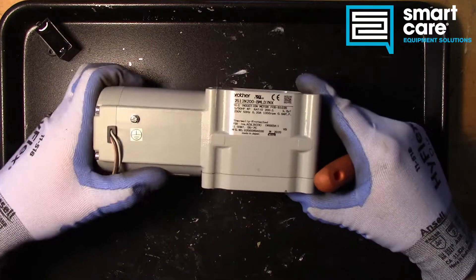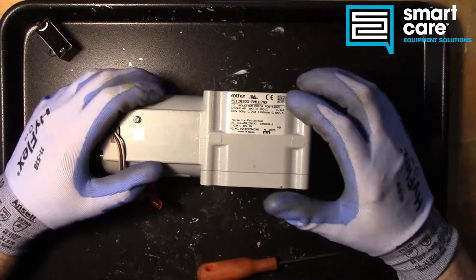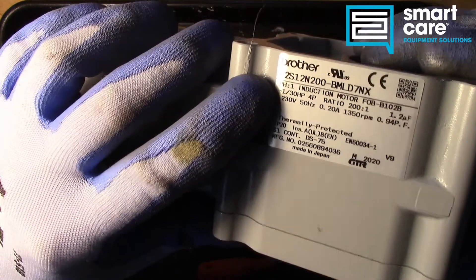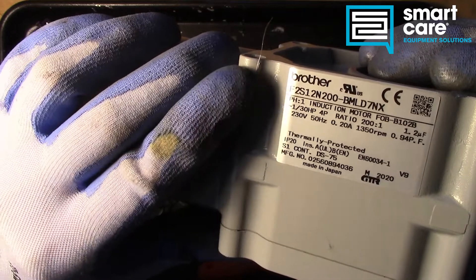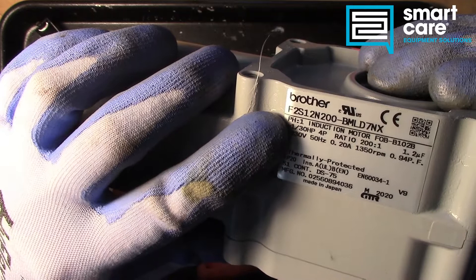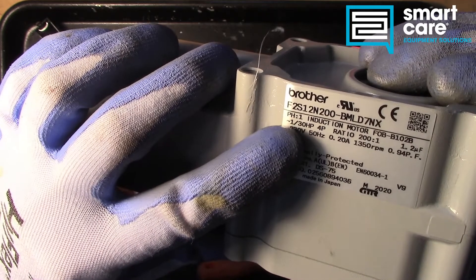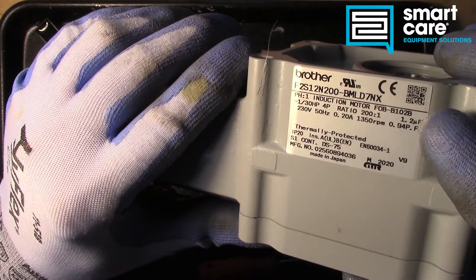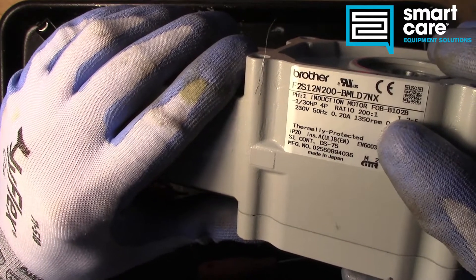The real question is here on the rating plate. So it tells us that we are dealing with a single-phase motor — pH is 1, it's an induction motor, it's 230 volt, 1/30 horsepower, has a 200 to 1 ratio, needs a 1.2 microfarad capacitor, and runs at 1,350 rpm.